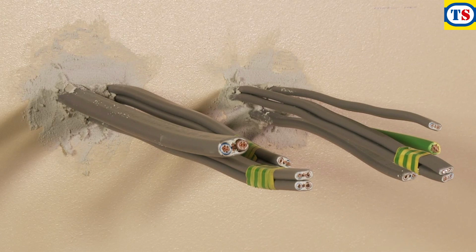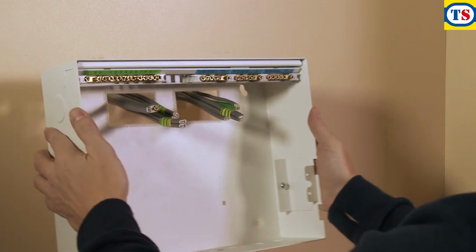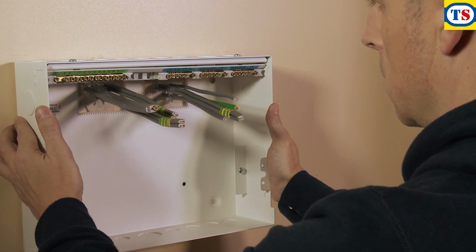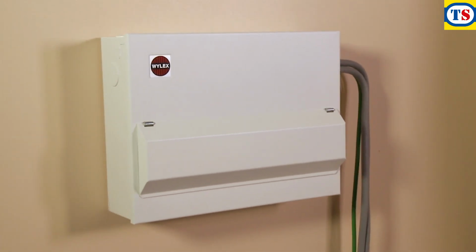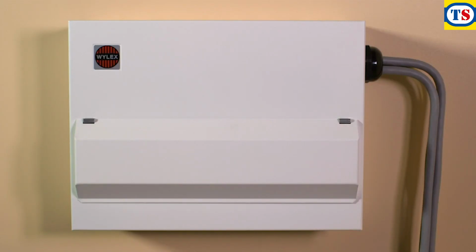In an installation with concealed or buried cables, using the rear entry knockouts automatically ensures that the IP rating on all elevations of the enclosure remain intact. Mains tails may also enter the unit through the rear entry knockouts or through a suitable mains tails gland.